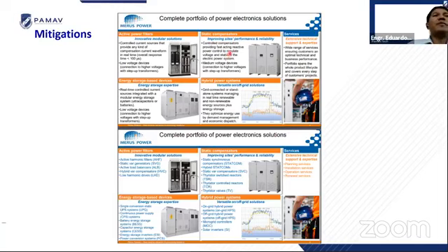Most of these are power electronics, which means if you have a distorted waveform, this system can also introduce a distorted waveform into your system in the opposite direction, so that the summation will be a good sine wave. But sometimes the installation is difficult because this equipment is electronic and should be installed in an air-conditioned, good place, because if you install it just outside, your active filter will become a problem too. So there are a lot of mitigations.